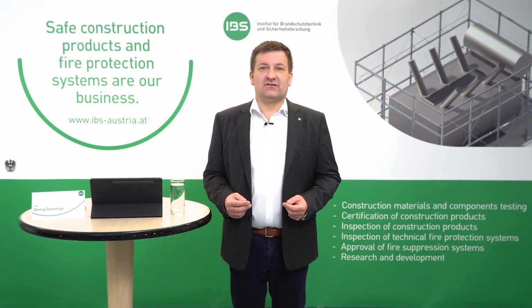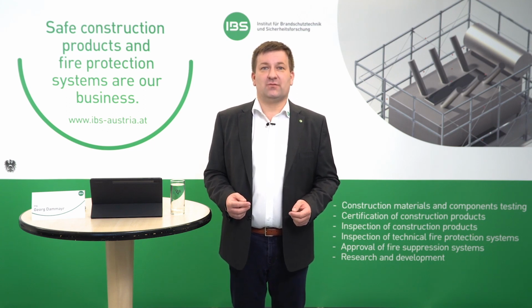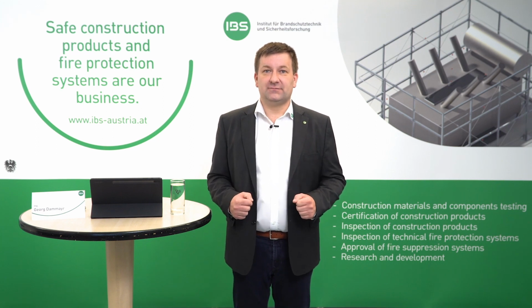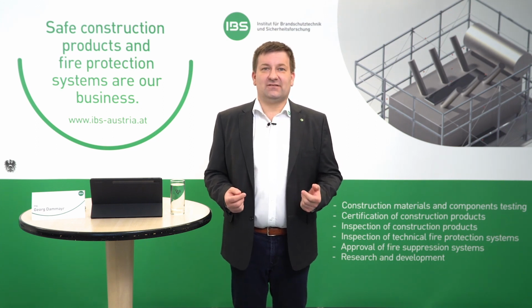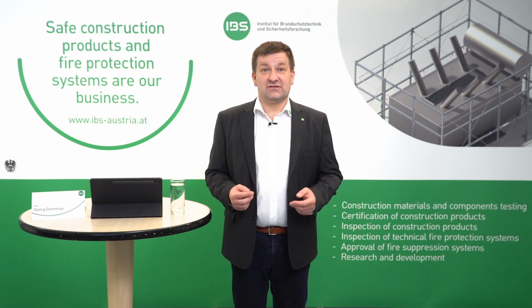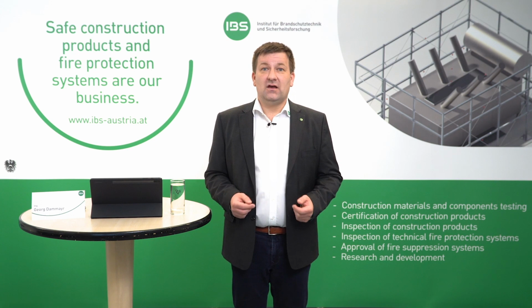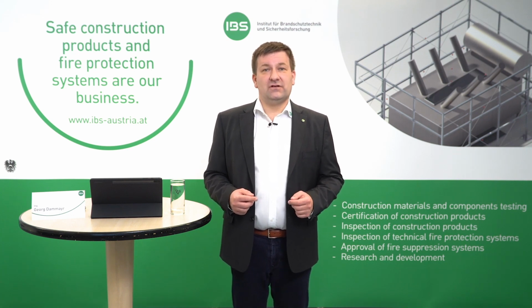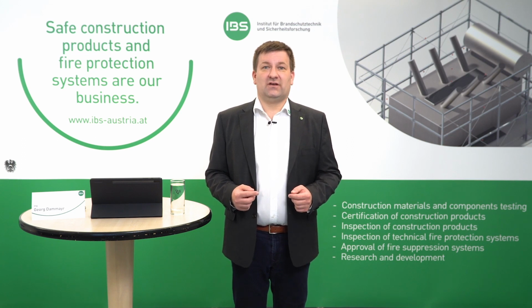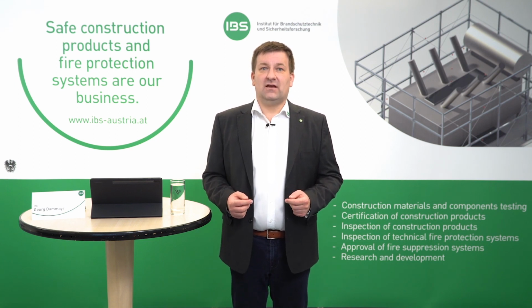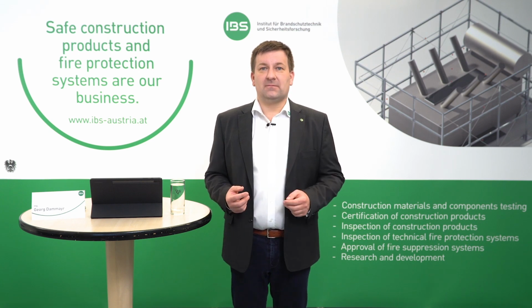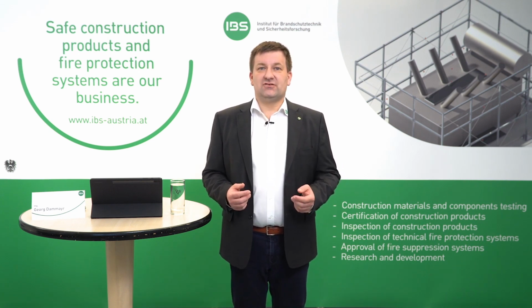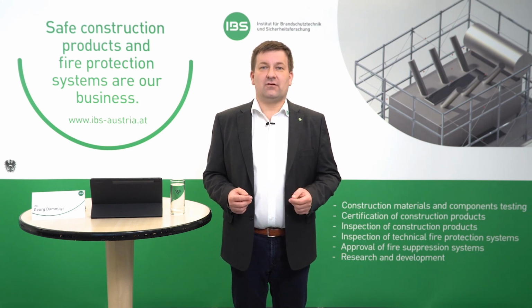We support manufacturers in testing and optimizing their product in full-scale fire tests. After 2 complete tests per scenario, the manufacturer receives an accredited test report in accordance with EN 14972 and an approval certificate. The proof of performance of the system during the approval test at IBS includes a complete functional test after verification of all required output, operating and alarm functions. This ensures that there are no leaks or faults.